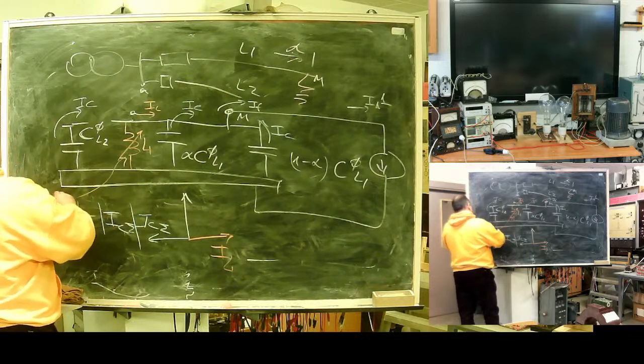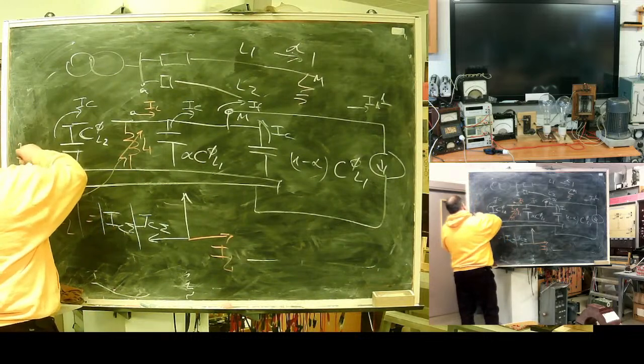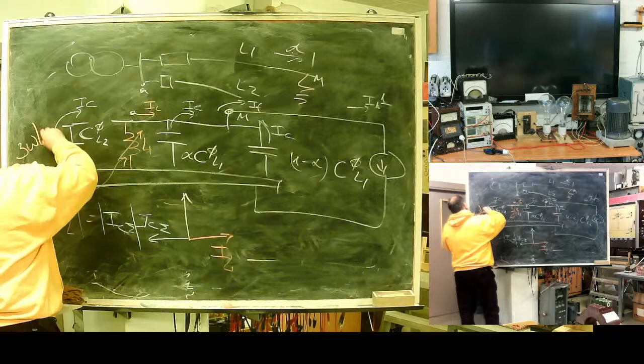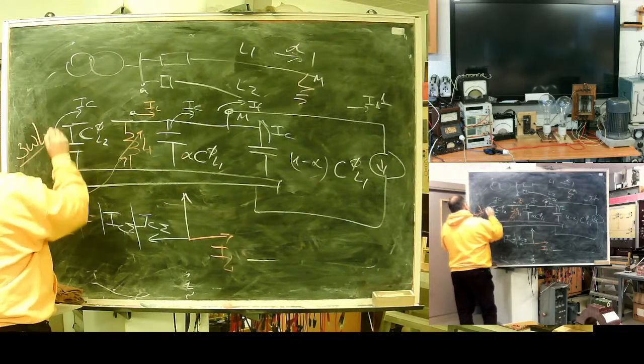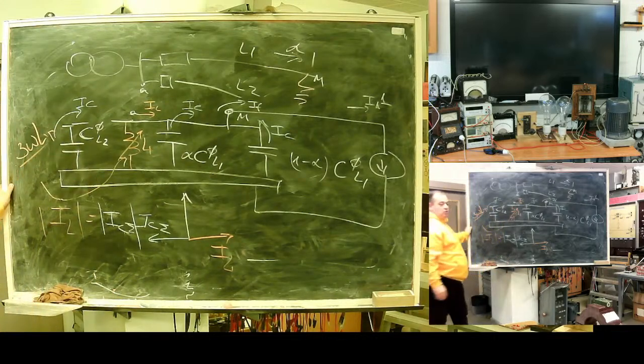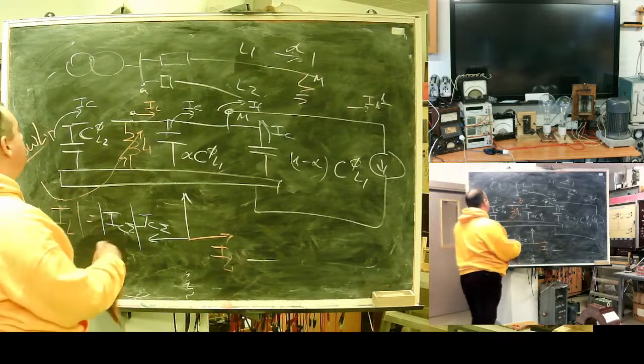This will be 3 omega L. Petersen or compensation coil. Compensated neutral. I can compensate capacitive earth fault current with inductive current, so the resulting current will be 0. How can it be done?